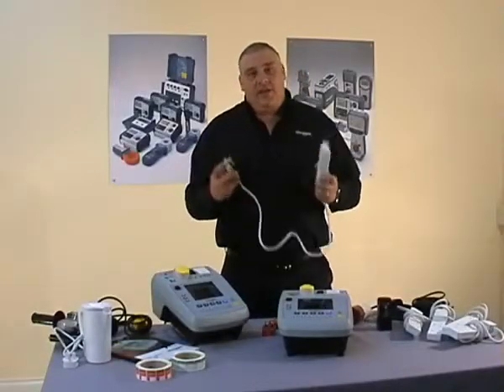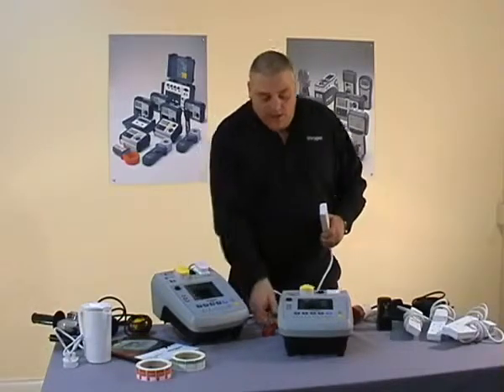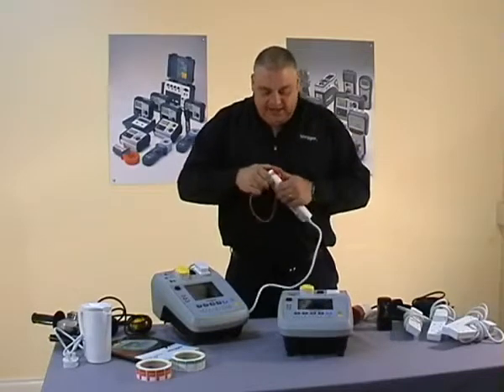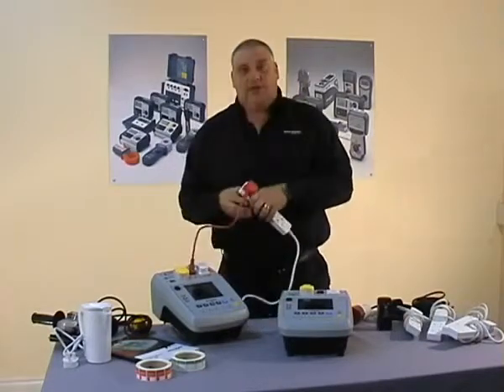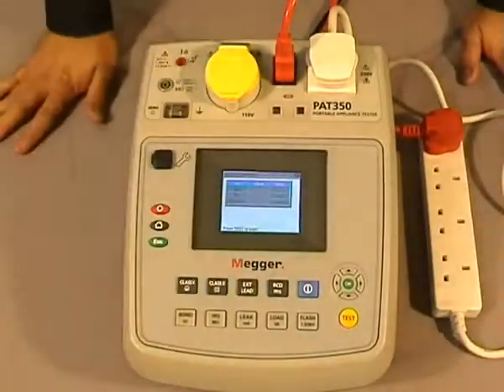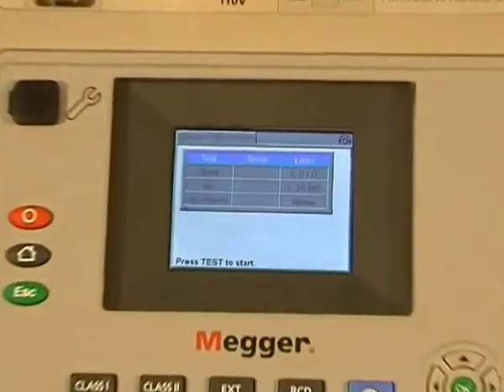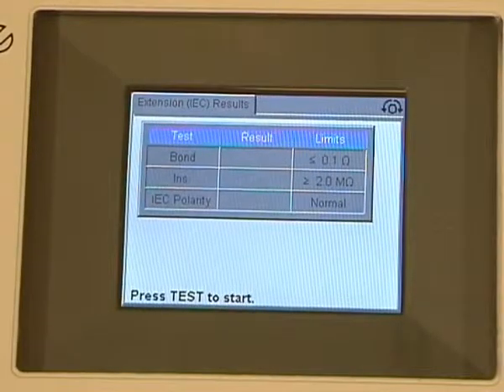To test our extension lead, we take it and plug it into the PAT tester. We then take our special IEC lead, which is supplied, plug it into the end of the extension and then back into the IEC port on the PAT tester. You press the extension lead button. On the screen you can see we have an IRF bond test, an insulation test, and this time we have a polarity test.